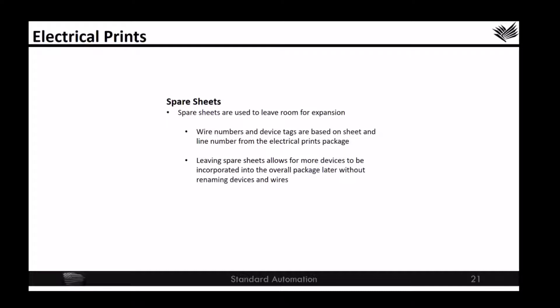One of the last components that we see in the electrical prints package are spare sheets. Spare sheets are used to leave room for expansion. As we talked about, wire numbers and device tags are based on sheet and line number from the electrical prints package. So if I want to add a junction box, I want to add that in an area where all the other junction box wiring is located. I don't want to have to add it to the end of the package and make my package confusing to navigate. So what happens is I'll include a spare sheet, and that way when a new junction box is integrated into the system, I can use one of the spare sheets because that allows me to include my device and incorporate it into the overall package without having to rename the later devices and wires. And it'll still be located where my other junction box wiring is. And so that's the point of the spare sheets.